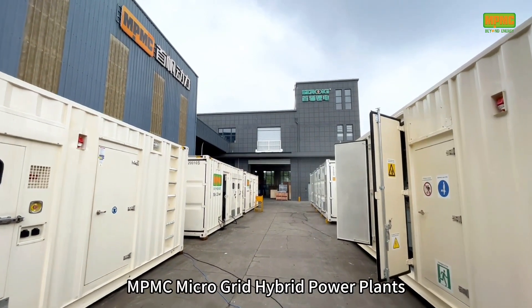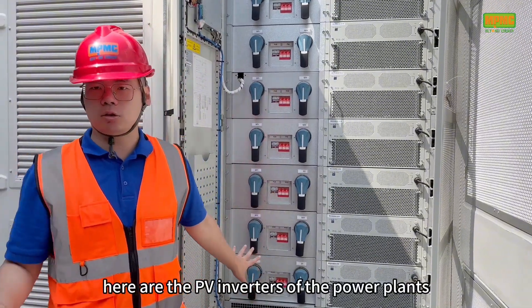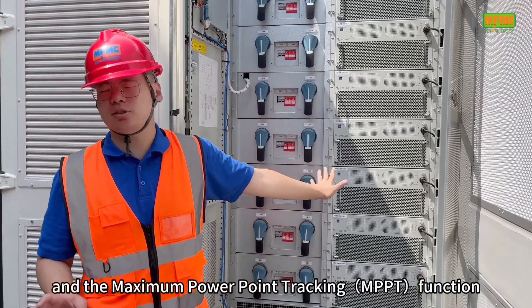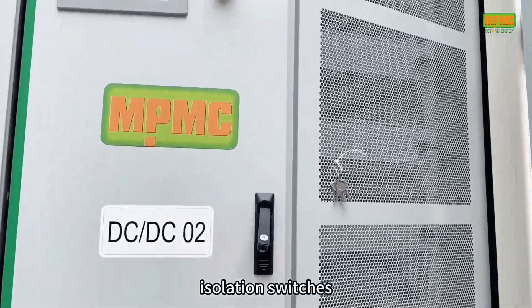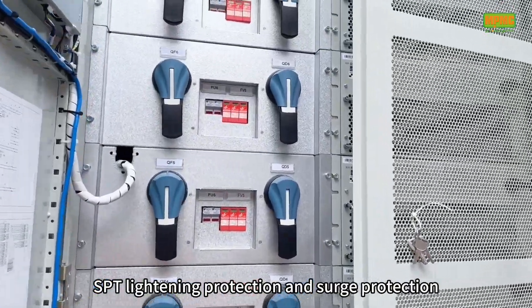Let's explore the details of MPMC microgrid hybrid power plants. Here are the PV inverters of the power plants. These inverters adopt DC-coupled design, with a maximum power of 50kW per module and maximum power point tracking function. Each module has separate input and output isolation switches and is equipped with SPD lightning protection and surge protection equipment.